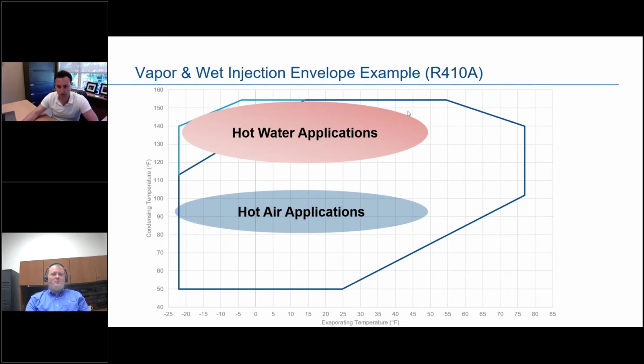Then here's the same envelope with the same conditions. As you can see, the hot water applications will fit inside that envelope whenever you have vapor, wet and liquid injection. This is another 410A example. It's a high pressure refrigerant. The R454B and R32 future options, which meet the low global warming potential requirements coming up for 2024 and 2025, will be able to have a similar envelope as well. There is work to go below -20 degrees evap temperature, saturated suction, which would allow you to operate at these conditions at lower ambient temperatures as well.